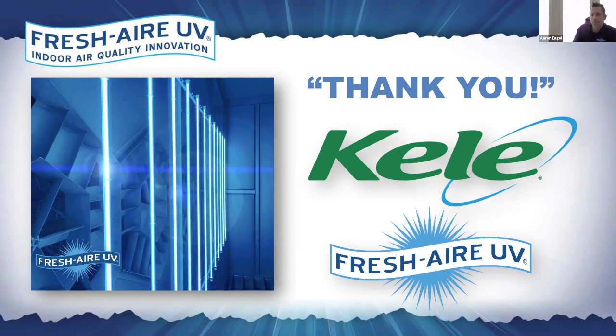It's polyester synthetic media, which typically, because our UV systems are mounted on the downstream side, the wet side of the coil, that's really where the beneficial installation location is. So you irradiate the coil and the drain pan. But in some instances, maybe limitations in space or whatever the case may be, you might have to put it on the upstream side. So you just want to be sure that if you are installing a UV system that's in direct contact with some sort of synthetic filter media, that you do take that into account. HEPAs are seemingly not an issue as well. So hope that answers your question.